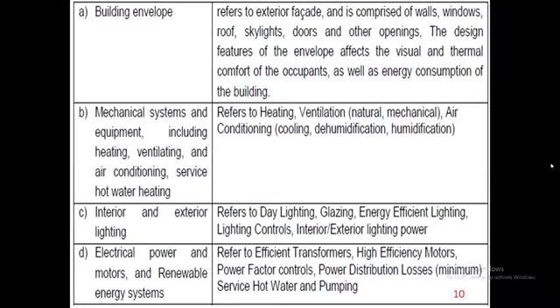But the power factor controls, again, whatever is said and done in theory, a motor is a balanced three-phase load in theory, but practically it is not happening. Definitely the neutral current is there, the negative phase sequence currents are already there. What I am giving as inputs or case studies is from the industry. So definitely a 3 CT operated power factor control for a given building, for any LT service or HT service, is mandatory. Why I am telling this now is, many industries have gone for only a single CT. They assume all the CTs are giving the same current. Definitely in harmonic loads where H5 and H7 components are there, the unbalance of current is very much more. You cannot control the power factor with just one CT sensing. It needs to be done with 3 CTs only.